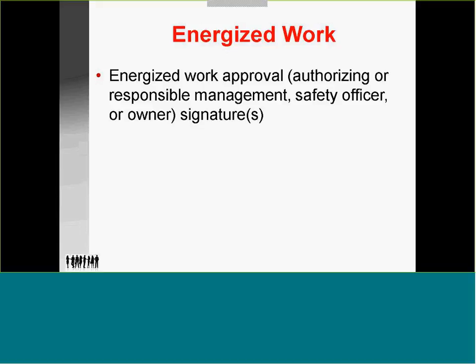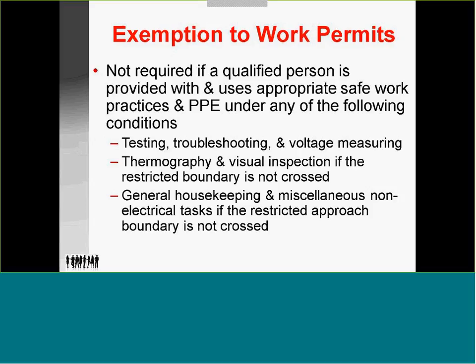After the crew sets it up, the supervisor signs off, then somebody from management. Exempt from the work permit, not required if a qualified person is provided with and uses appropriate safe work practices and PPE on the following: troubleshooting, voltage measuring, photography or infrared photography, and visual inspection, if the restricted boundary is not crossed. It also does not require a permit for housekeeping and miscellaneous non-electrical tasks if the restricted approach boundary is not crossed. Only a qualified electrical worker may cross the restricted boundary.